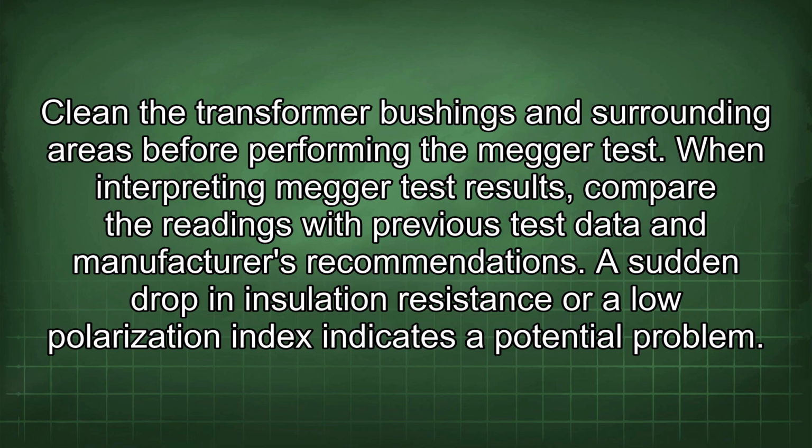When interpreting megger test results, compare the readings with previous test data and manufacturer's recommendations. A sudden drop in insulation resistance or low polarization index indicates a potential problem.